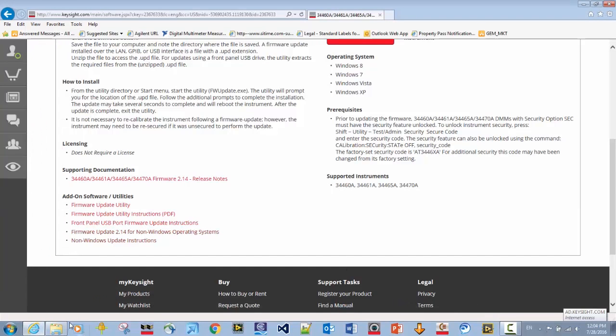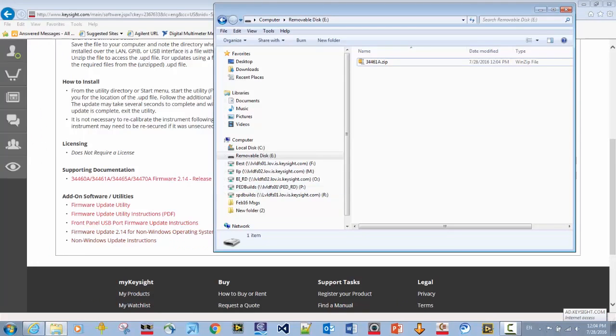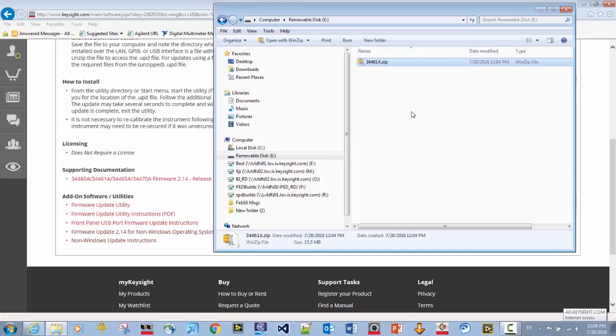Then by bringing up the Windows Explorer, you can see that we have the zip file that has been downloaded onto the thumb drive. Now again, this is being shown using Windows, but for most other operating systems that have comparable Windows Explorer types of functions, you'll be able to do the same process as far as downloading the zip file and updating the firmware.